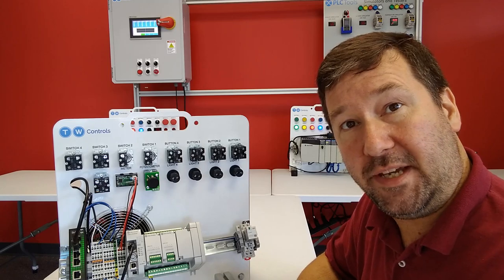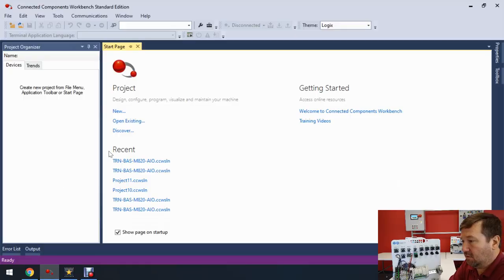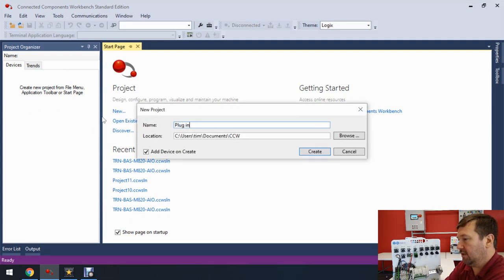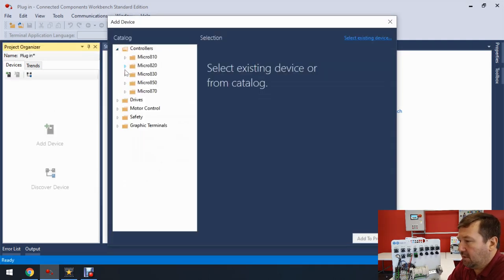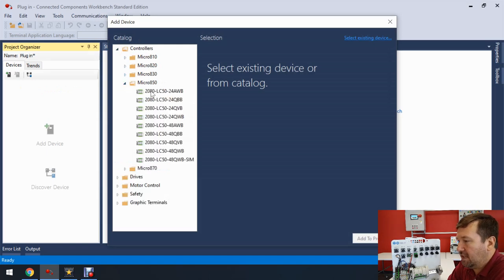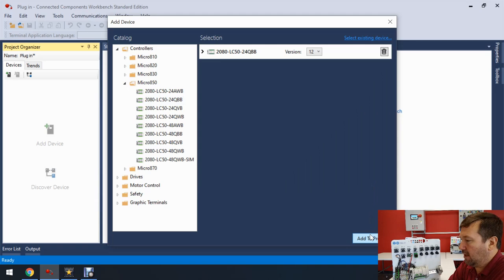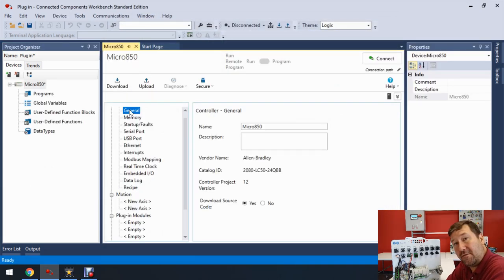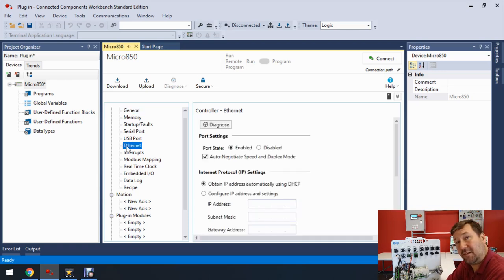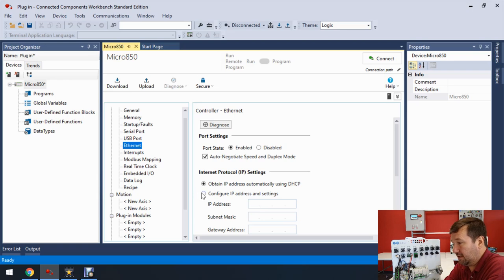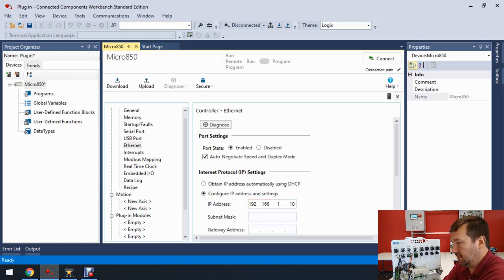Now let's go into Connected Components Workbench and configure them. Let's start with a new program — we'll call this 'plug-in' — then open up Controllers and select the Micro 850, specifically the 2080-LC50-24QBB, and add it to the project. First thing, just like in all our Micro 800 videos, go to Ethernet and configure it, because if you download without doing that you'll set your PLC back to DHCP. We're going to configure the IP as 192.168.1.10 with a subnet of 255.255.255.0.